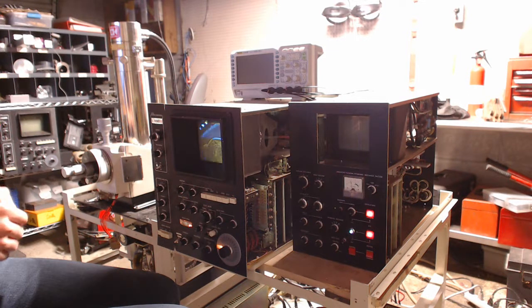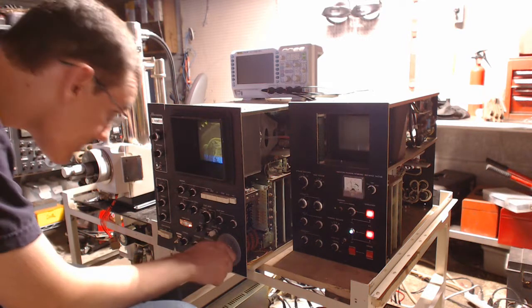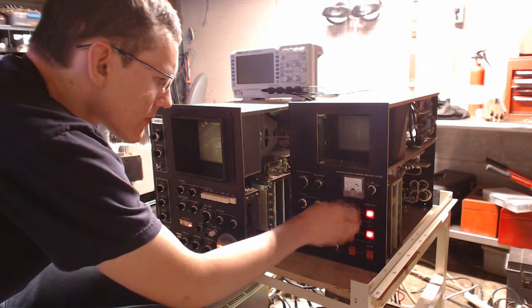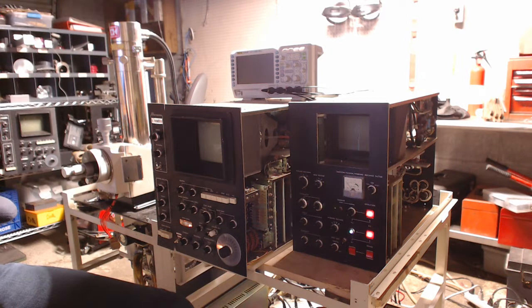So, I think I'm pretty happy with how I've got my... I'll go ahead and take the kV up one more time. Go to 15 kV. But I think I've got the stigmators adjusted as much as I can with the Scintillator in its current condition. It's just really hard to see the difference between this is the edge and this is not the edge, because the edge is really fuzzy, regardless of what you do, because of the noise of the Scintillator. Because when you zoom in that far, you have to reduce the electron beam spot size significantly, and when you reduce the spot size, you reduce your secondary electron returns, so you have to increase your contrast, which increases the noise amplification coming off the Scintillator.